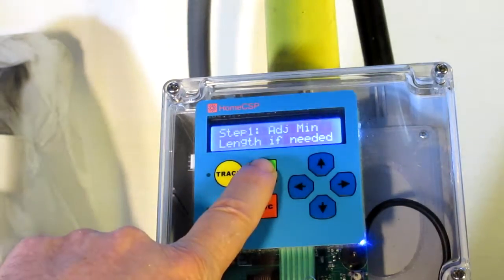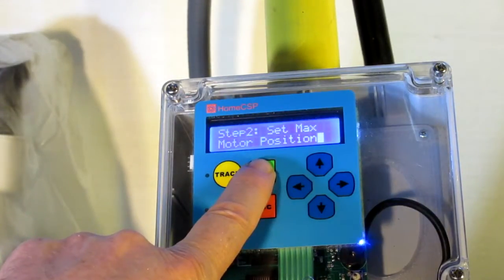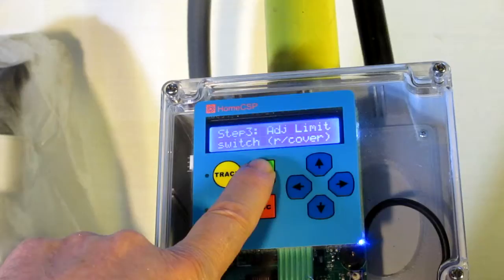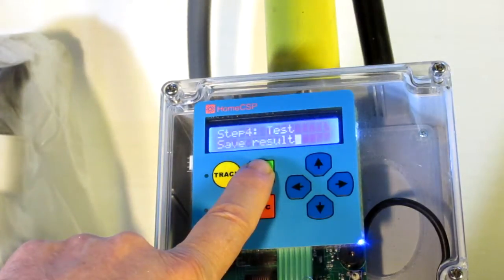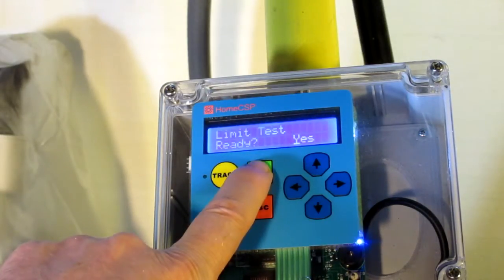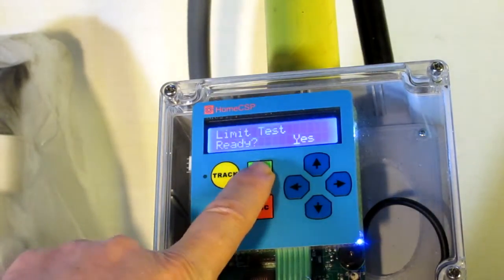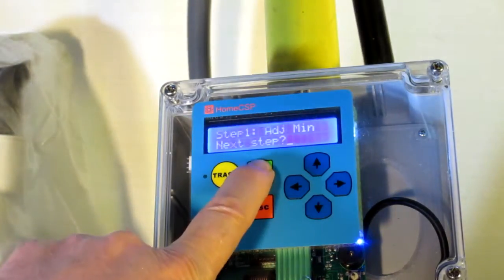And as before, adjust the minimum length if needed. And then we're going to drive to the maximum position. Adjust the limit switch if needed. And save the results. Of course, this has already been tuned up, so we don't need to adjust the length or set the limit switch. We're ready to go though.